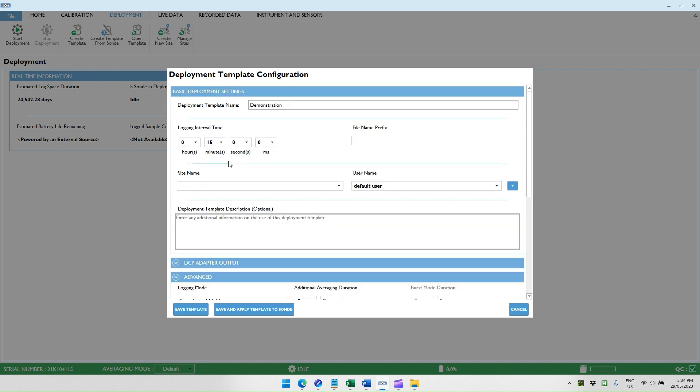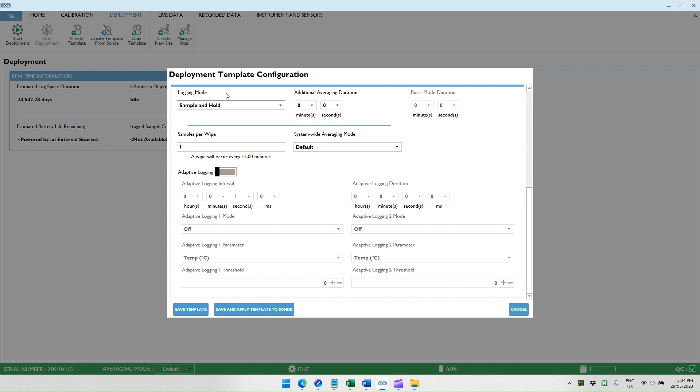The advantage of using the internal logging is that the sonde records data as well as the AI-1 recording data. If the AI-1 has a failure for any reason, the sonde will still keep a record of the data, such as if the AI-1 was damaged or the cable was damaged and the AI-1 failed to get or receive data from the sonde. You could realize that through the telemetry system and could still manually download data from the sonde and upload that to the data historian. We do recommend that you use logging on the sonde and sample and hold as a logging mode so that the same data is stored on the sonde as well as being stored on the AI-1.